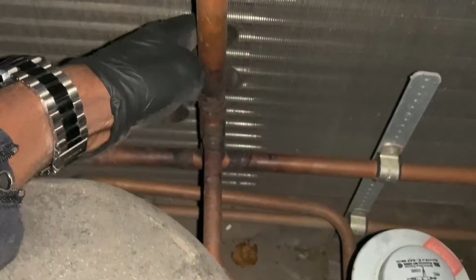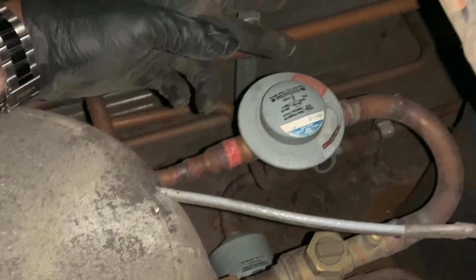Now, the second pipe is the liquid line outlet, the liquid line out from your condenser, or the condenser outlet, also called liquid line leaving condenser. And unlike the discharge line, the liquid line leaving the condenser passes straight through the valve only. It is not teed off. So in the bottom here, you can see this right here is a liquid line.